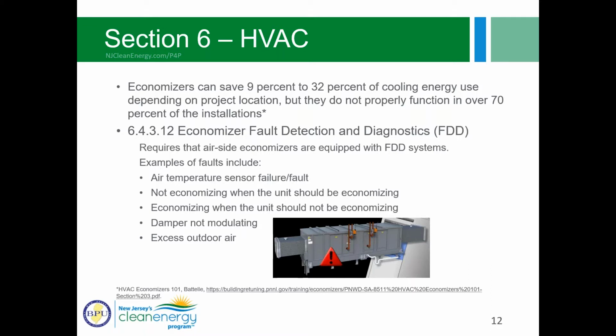So what are some ways that we could make sure that these continue to operate? 90.1 now requires fault detection and diagnostics for economizers. So assessing a couple of different values: are the temperature sensors working during the conditions when the economizer should be functioning? Is it actually doing that? Are the dampers modulating appropriately? Is there excess outdoor air being provided when it should not be economizing? Again, these are all things that would help to support incentive number 3, the performance-based one.